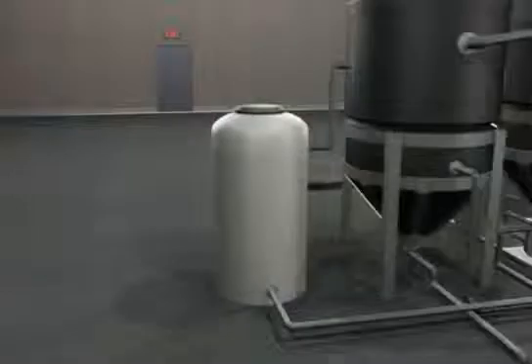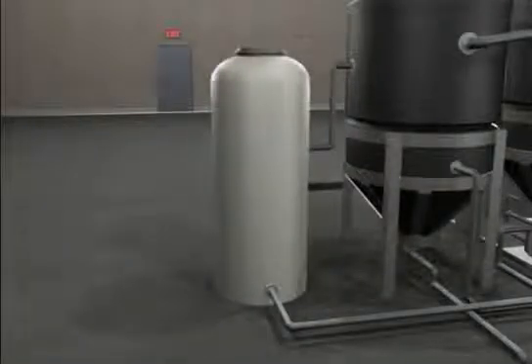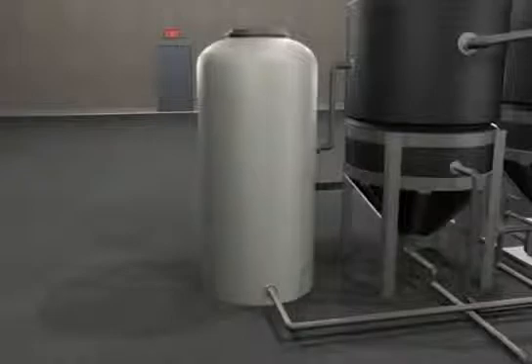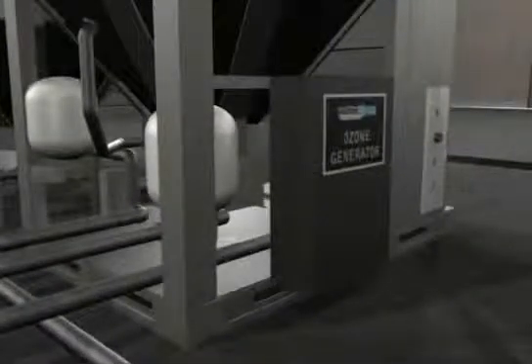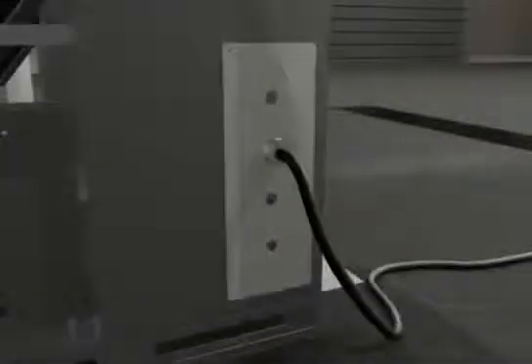The recycled water holding tank is sized based on the specific application requirement and houses the necessary float controls for reuse. This tank is also treated automatically with ozone for further sanitation of the water and odor control prior to reuse. A powerful four-bulb ultraviolet ozone generator provides ozone via a special mixing system that effectively treats and sanitizes 99% of the stored water to prevent odors. A pressurized tank and transfer pump supply treated water back to the pressure washer or hose on demand.